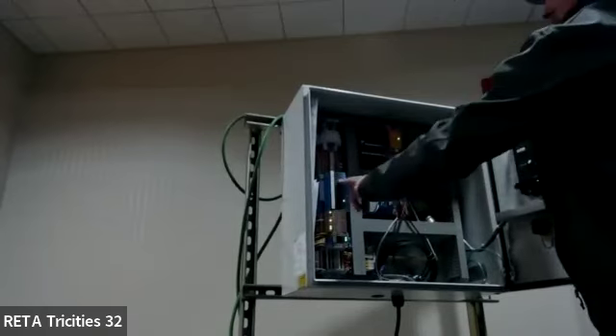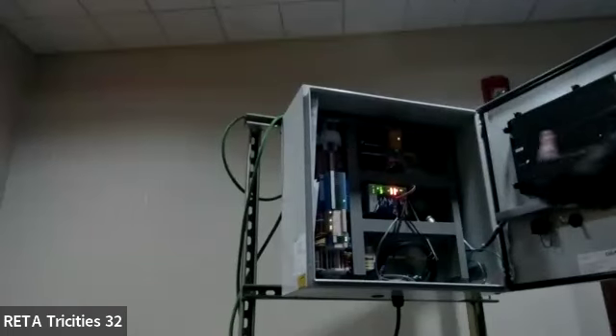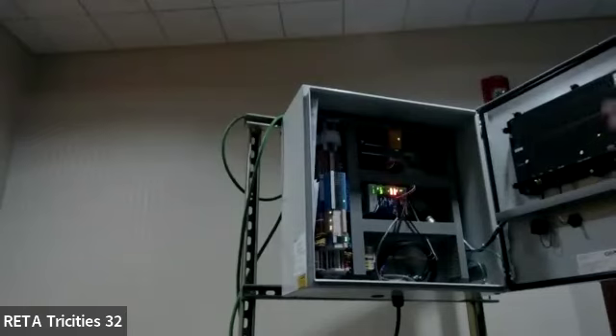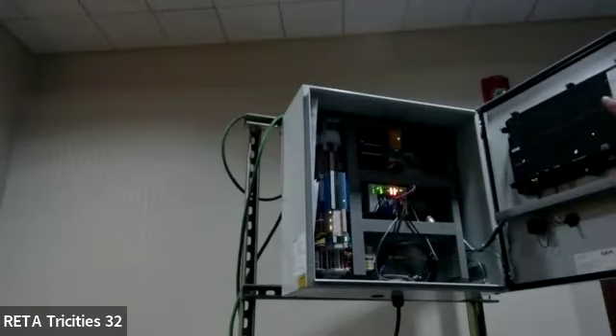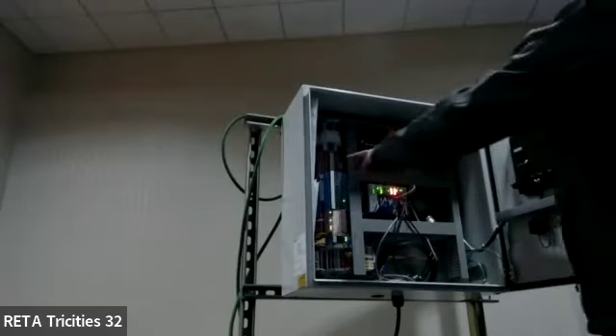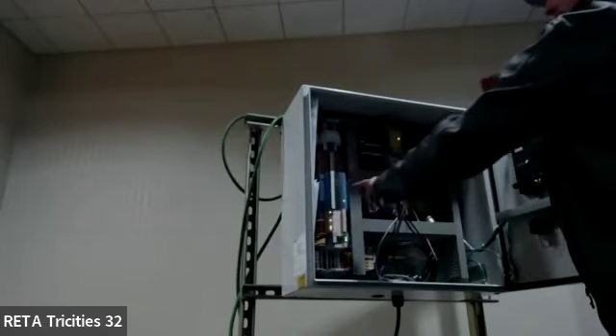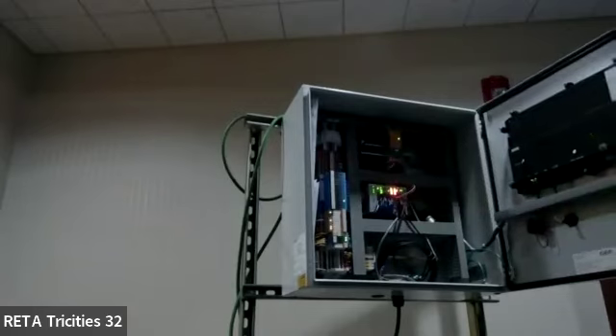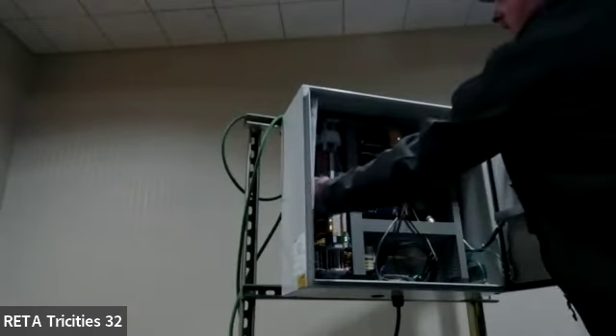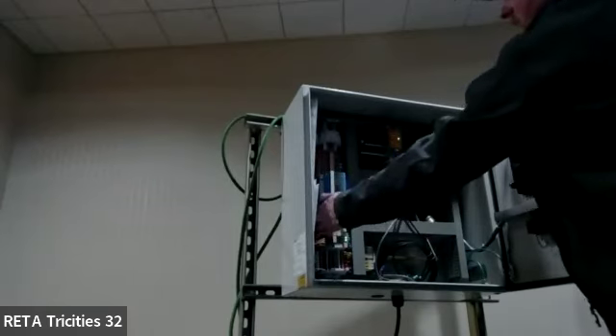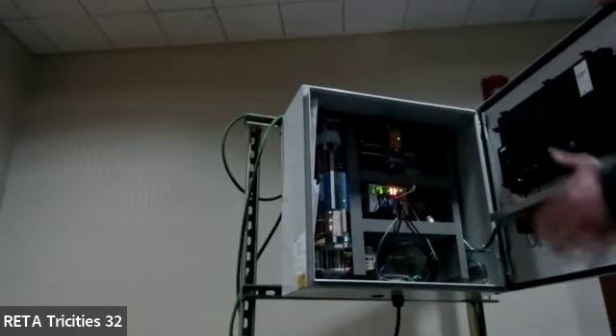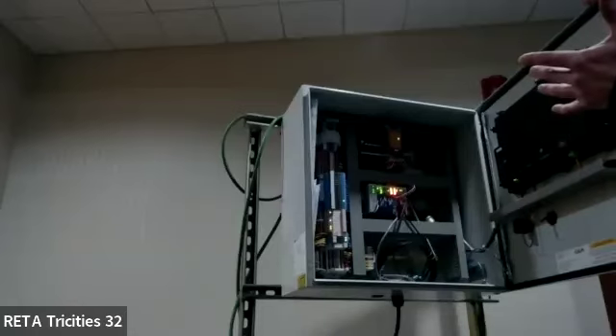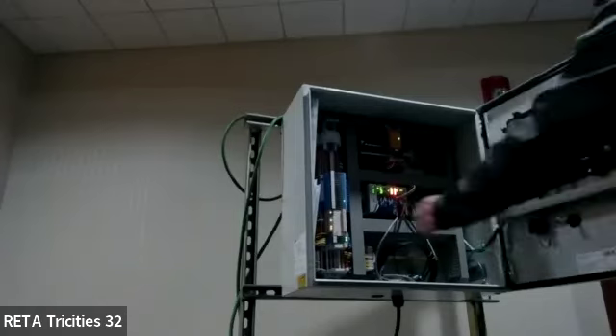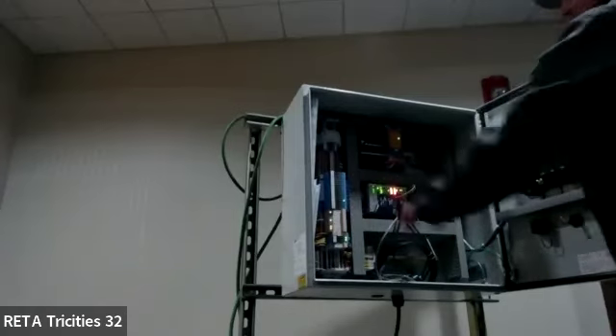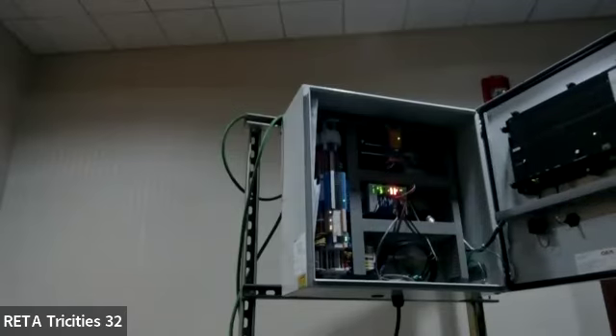Okay. Well, what I've seen the most is people try to jump out the high level to do a test run or when they're first starting a facility, you want to bump check a motor, things like that. I've seen many times where they'll take power from 106A and put it on this side, which will short it. This side is the 120 volt side. This is your normally open, normally closed side, dry contacts, which you can run 24 volt, 120 volt, whatever you want on that. But this side right here is strictly do not put 120 volts to that 24 volt side.